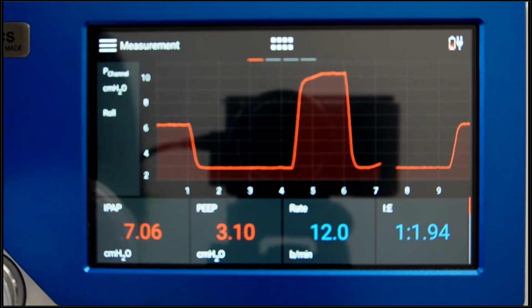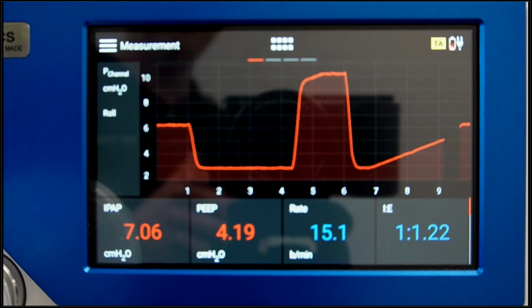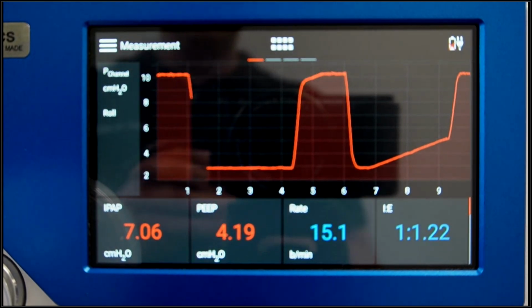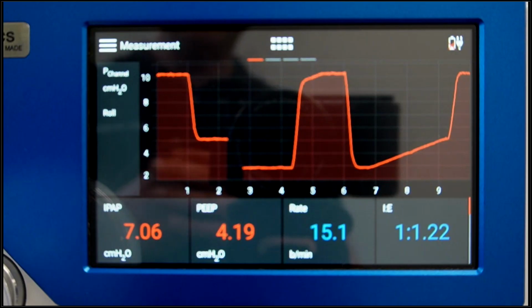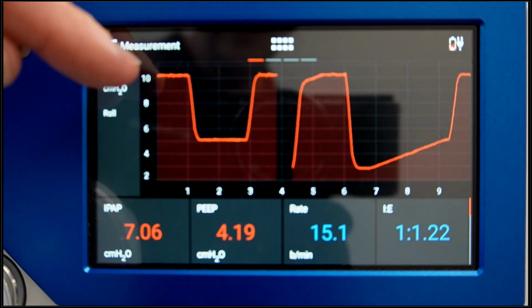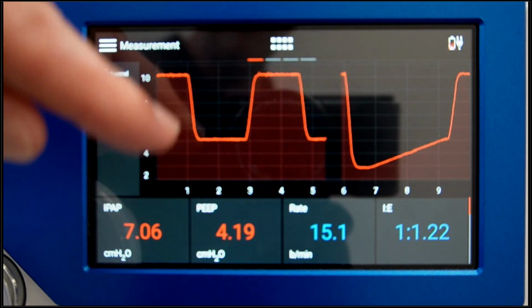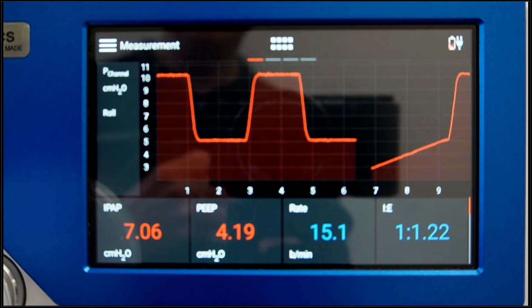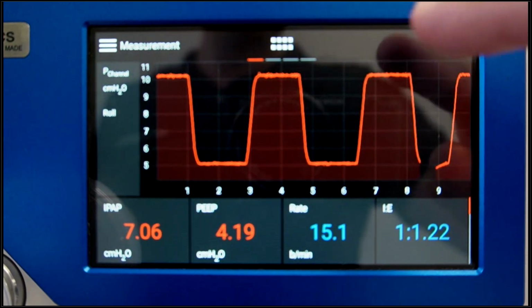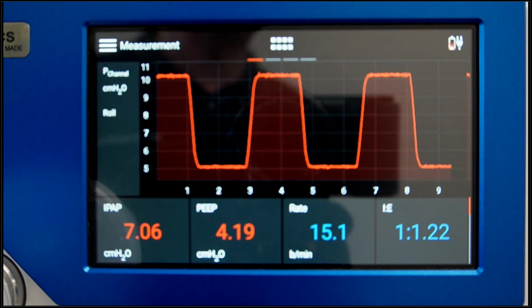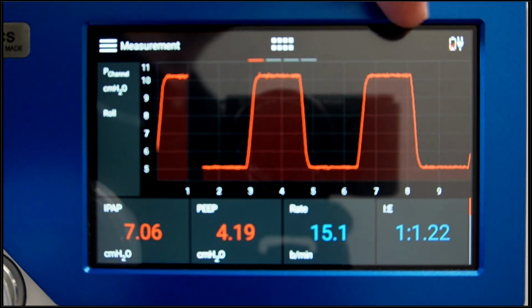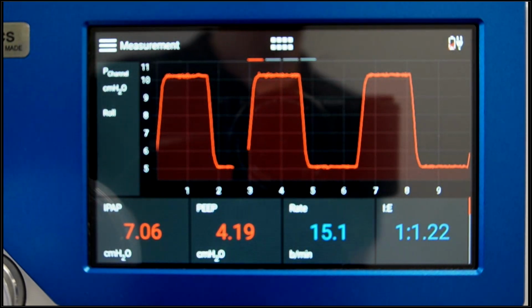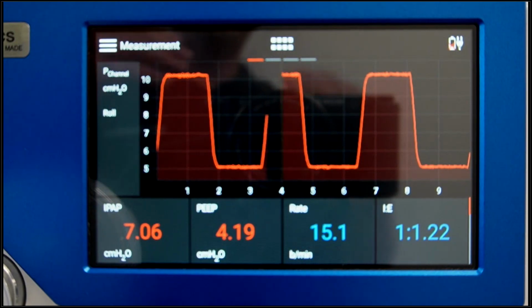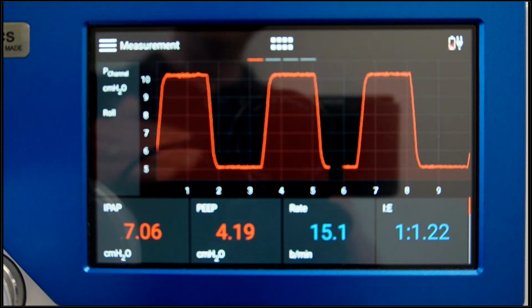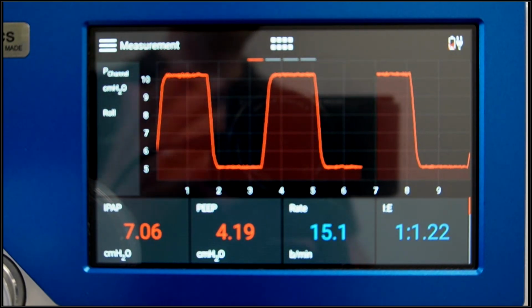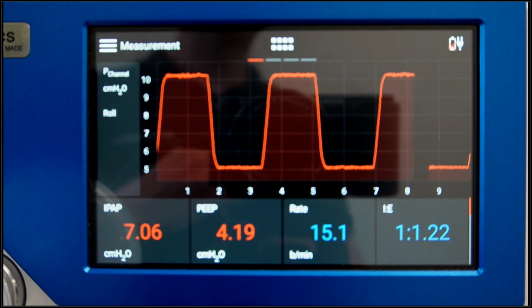And what you will see as soon as I apply these settings, now you can see the pressure level is higher. So I have an EPAP of 5 and IPAP of 10. And suddenly you can see my gas flow analyzer is no longer able to trigger. So there's no trigger indication visible anymore. Why is that? Because my start trigger is now on a level below my EPAP. So my analyzer is no longer triggering.